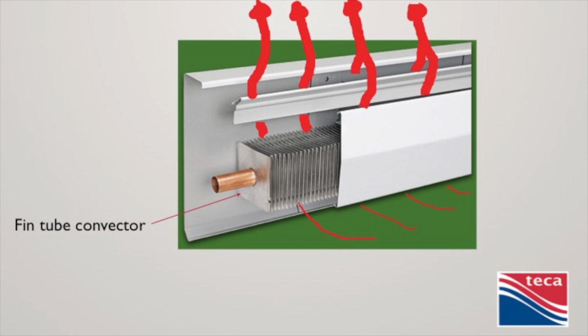People call them radiators. Over there by the wall, there's a radiator on the wall. It's not a radiator. It's anything but a radiator. It's a convector. Oops, back we go. Yeah, so here it is. This is what happens. Oops, sorry, hitting the wrong button here. So cold air comes in, gets heated up by the aluminum fins. You've seen this a million times. This is all convective. This plate in the front is really not even touching this. Sure, you might get some radiated heat from here, but realistically, it's a convector. You're heating air, and it's migrating up the wall, and so you're usually using it on the perimeter.